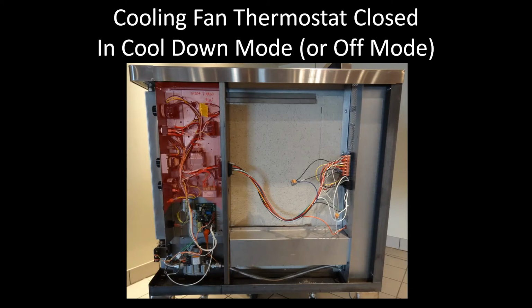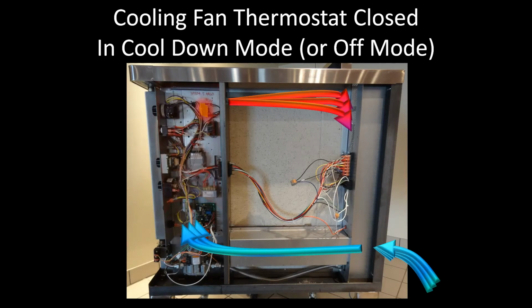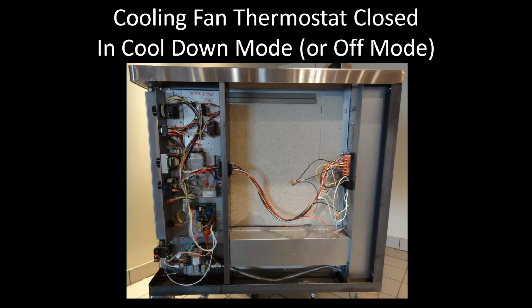While in cool down, if the control panel is still warm, the cooling fan thermostat will close at 110 degrees and feed voltage to the axial cooling fan. The cool air pushes the warm air out of the rear of the unit. Once the panel is below 90 degrees, the thermostat will open and the fan will stop. While in cook mode, the axial fan is on all the time, but in cool down or off mode, the cooling fan thermostat controls the axial fan.